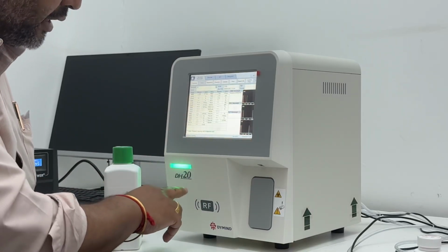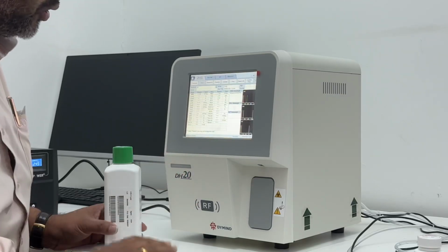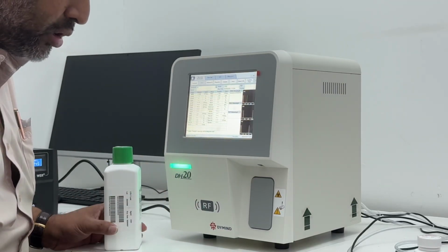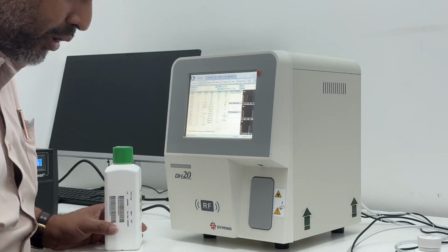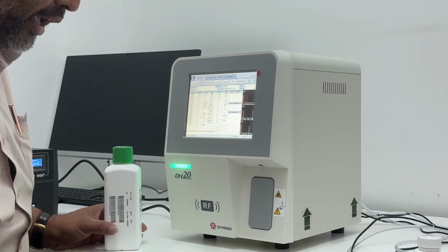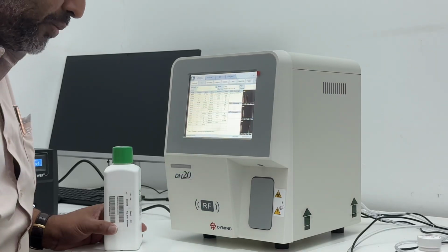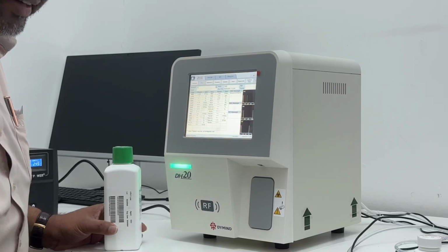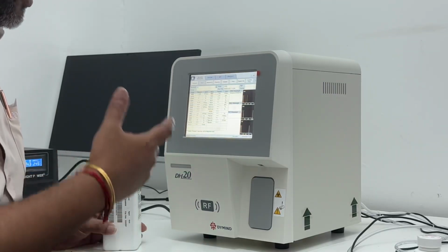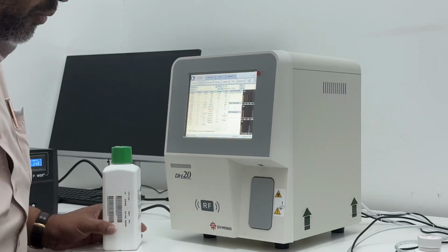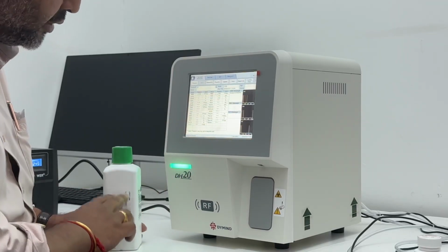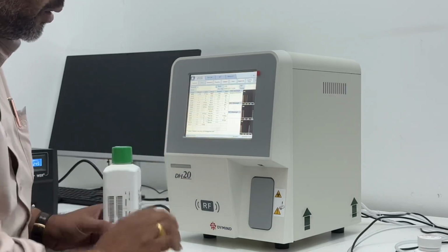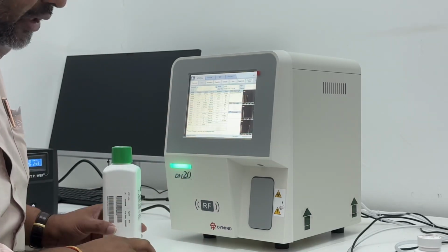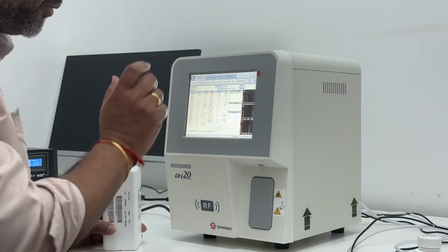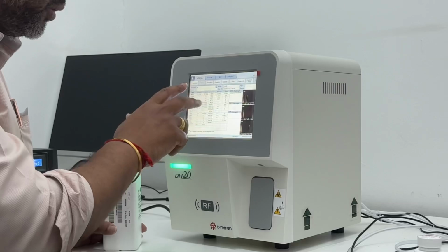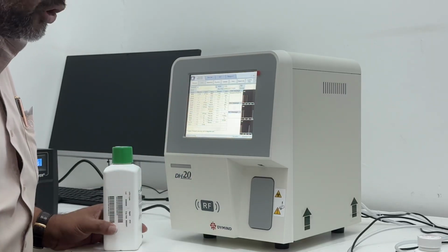And the second thing, this RF card, the function is, whenever we activate, even though the reagent has 2 years expiry, all the reagents, any brands, have a stability once we open. For this particular reagent, the stability is about 100 days. But for the safety features, the design is such that once we fix in the new diluent or lyse, the machine will only alarm after 60 days from the date of install. The machine will alarm reagent expired. So once the reagent expired, we need to change to the new reagent.